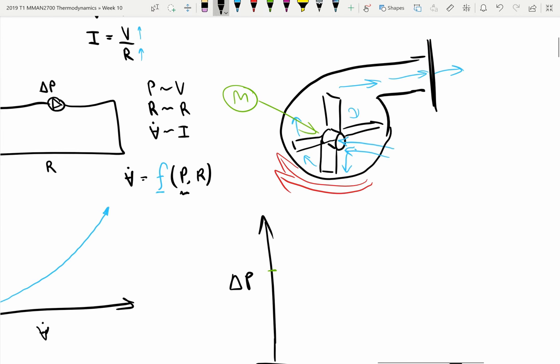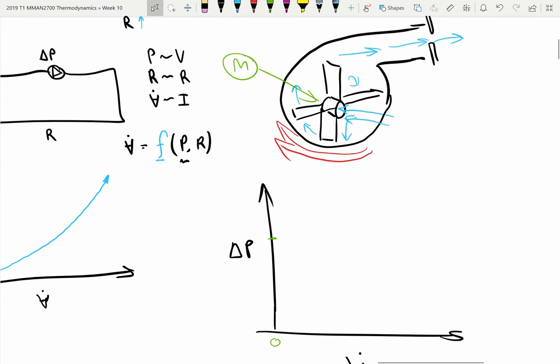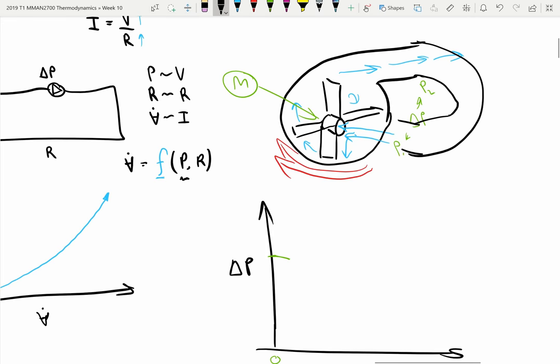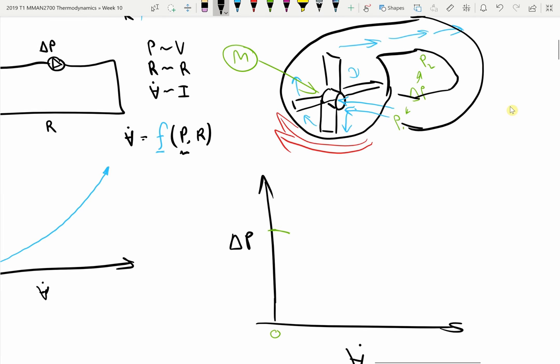Now let's open this up and make it an orifice plate with a small hole, allowing some small volume flow. When I say ΔP, we're talking about the pressure before the pump and the pressure immediately after the pump — the difference between those two values — the pressure being induced by the impeller. You'll get some small volumetric flow rate at some lowered pressure. We could continue this process until we had essentially no resistance, and we'd have some maximum flow rate the pump would be able to produce.